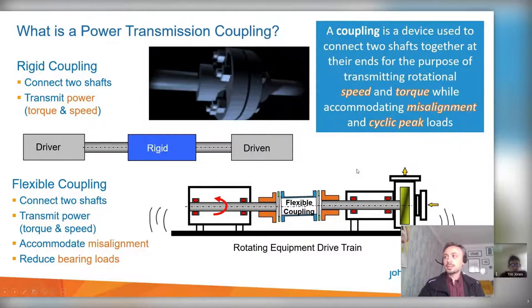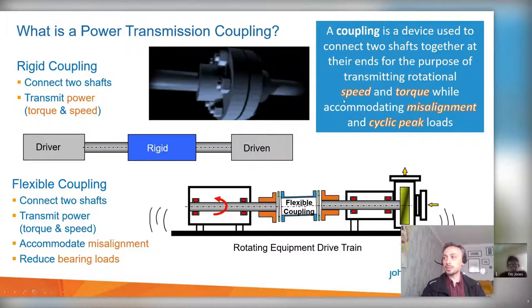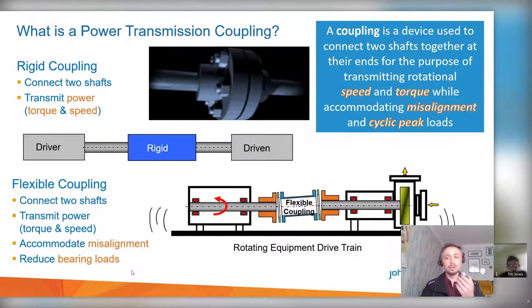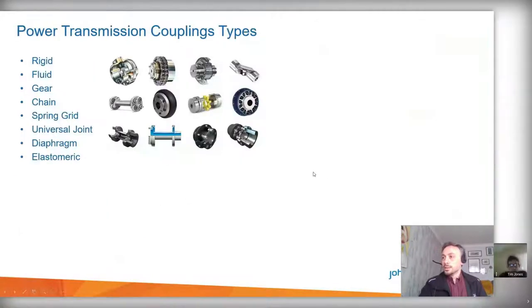A coupling is basically a device — simple or complex — that connects two shafts from their ends, with the purpose of transmitting power through rotational speed and torque. The simplest coupling is the rigid coupling: a rigid piece connecting two shafts, where a driver machine drives the driven machine. The key difference with a flexible coupling is that it can also accommodate misalignment, which reduces bearing loads. Industry often involves high operating speeds, high torque, and significant misalignment, so flexible couplings help to reduce lateral forces and bending moments on bearings.